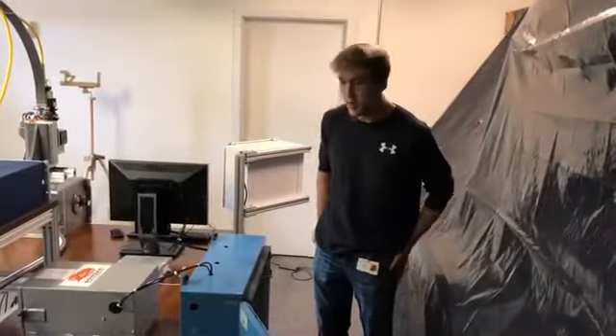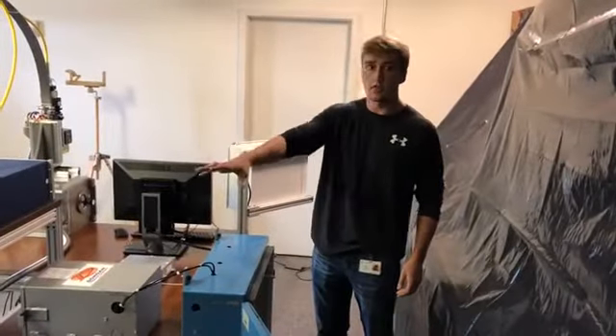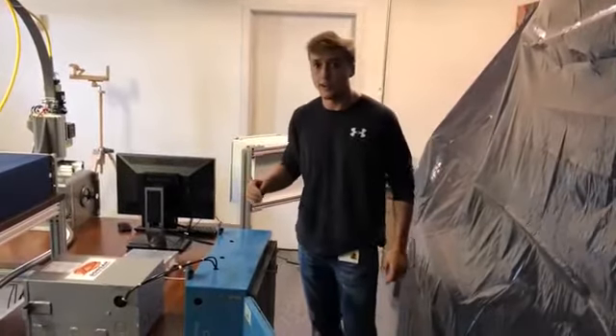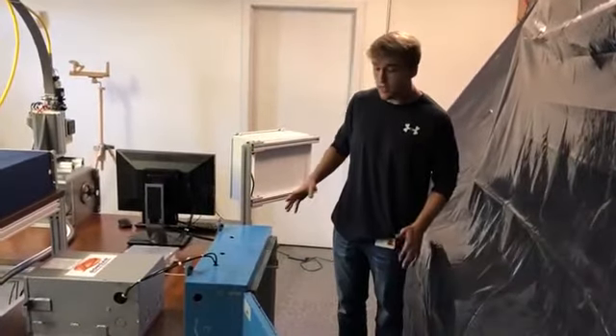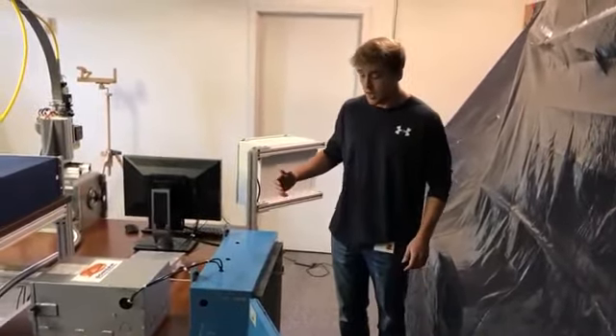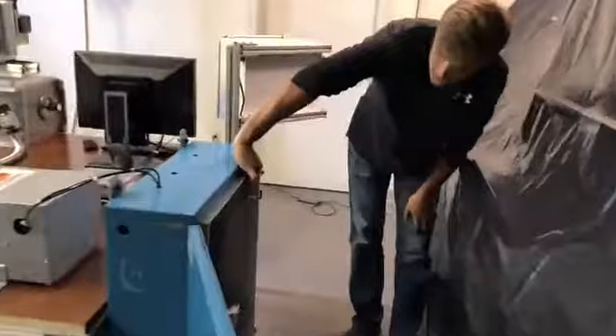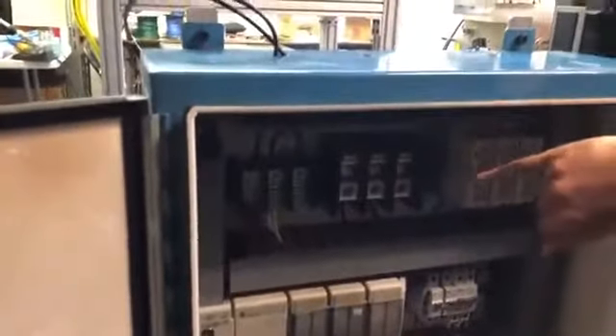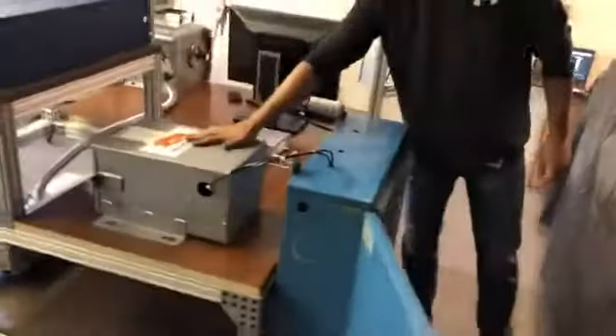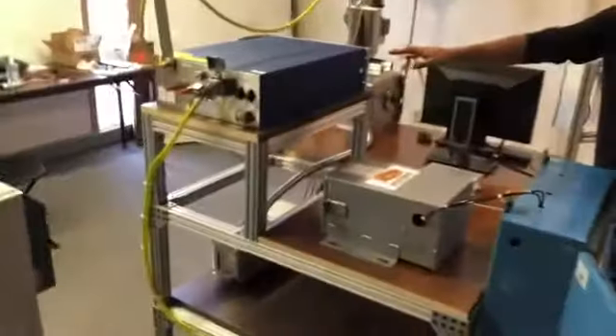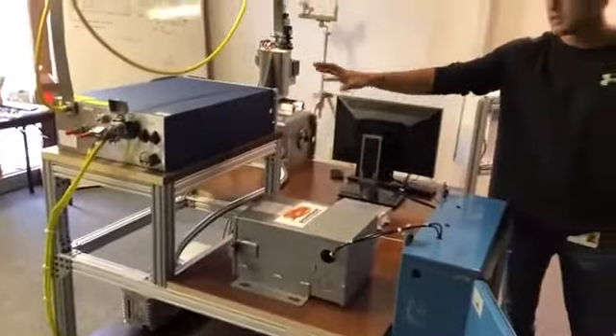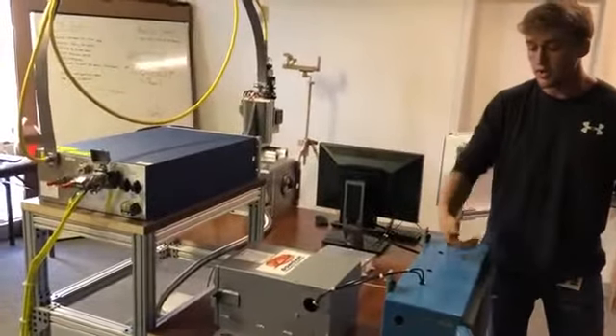Alright, so a little bit about our power distribution. Separately, we're going to have our chiller, which is going to have its own 480 3-phase line. Other than that, we're going to have a separate 240 volt line coming through here. As you can see through the cabinet, we're going to have our main fusing, which leads to our first power distribution block. This 240 is going to lead both to our single phase transformer as well as our laser generator. The laser generator has internal fusing, so nothing in regards to the cabinet.